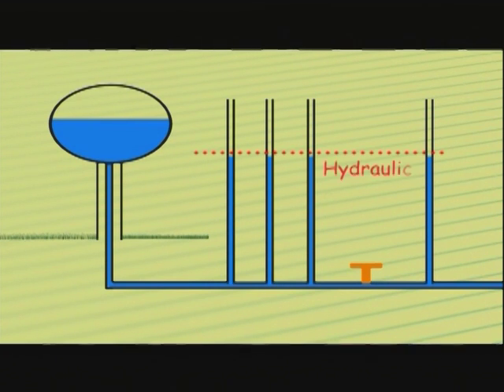This red line is called a hydraulic grade line. Generally, we use feet with tanks and convert to PSI. The result is going to tell you, based on the flow through the pipelines, how much pressure you have at any given point in your distribution system.